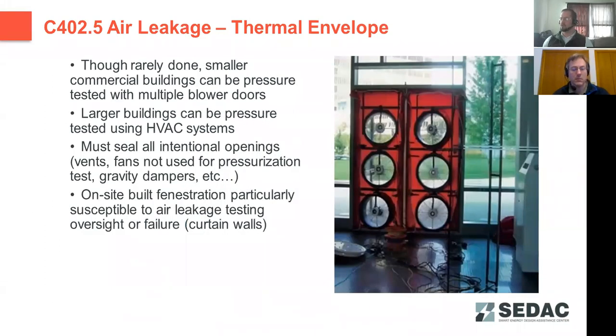Blower door testing is very popular in residential because of that pressure testing requirement for residential buildings, and it's growing in commercial. We like to see pressure testing because it can reveal a lot of hidden issues that can otherwise be missed with the other compliance methods, which rely on plan review, on-site inspection and visual inspections. So even though it's not as common in commercial, it is a growing trend, especially in smaller commercial buildings. For very large commercial buildings, they either have trailer-mounted fans, such as the blower doors you see in this picture, or they'll use the HVAC system itself. They'll set it up to pressurize the building to meet that 75 pascal pressure testing requirement.